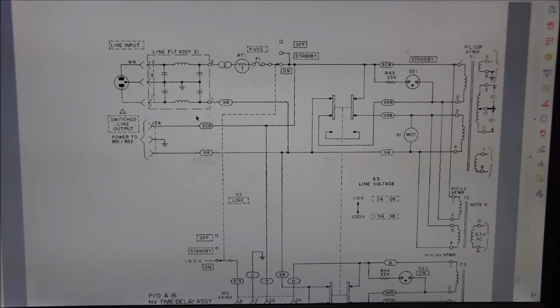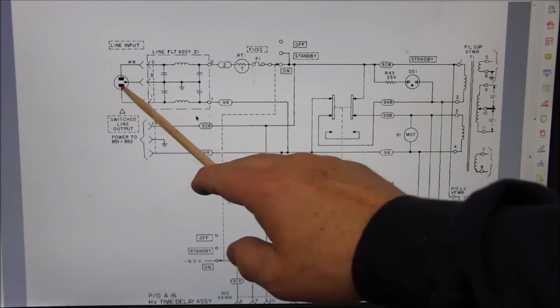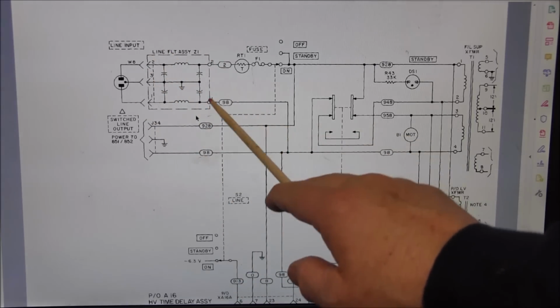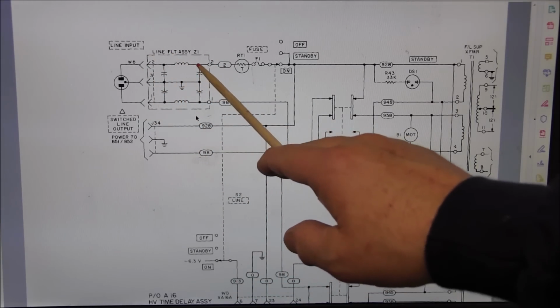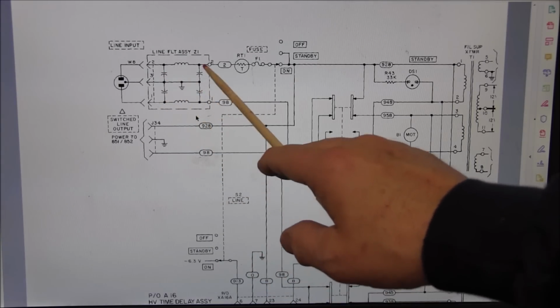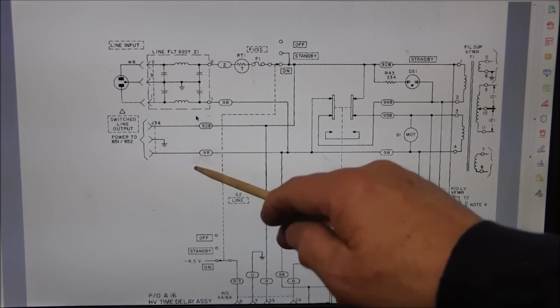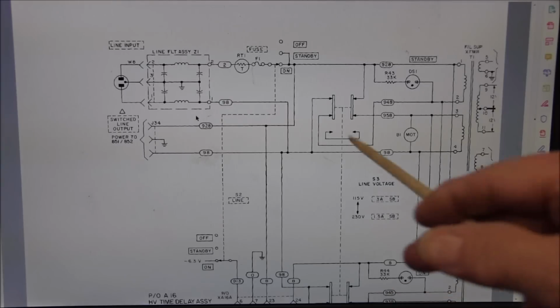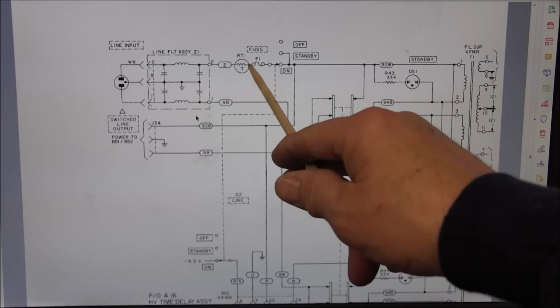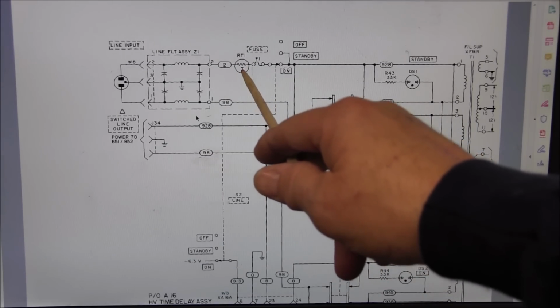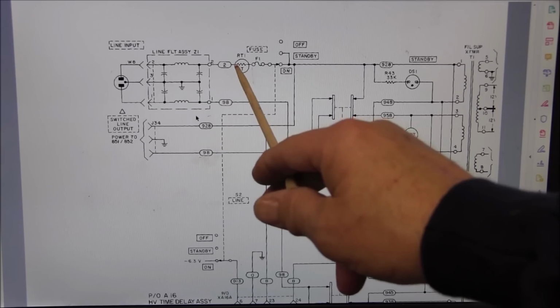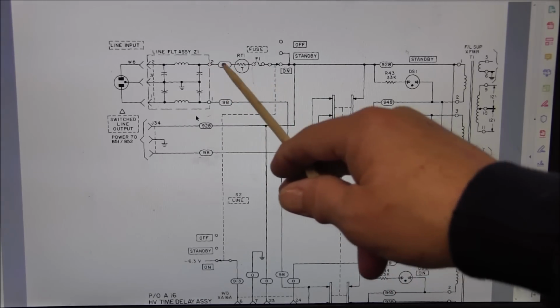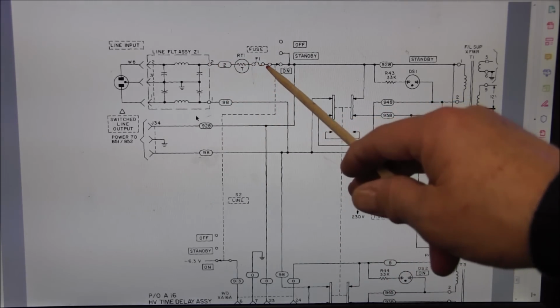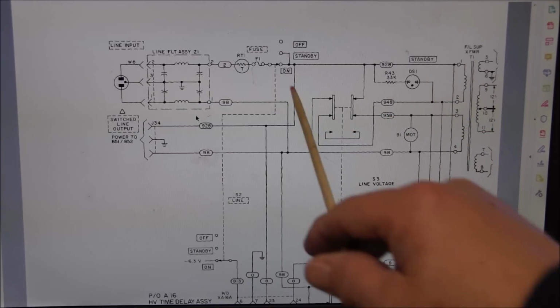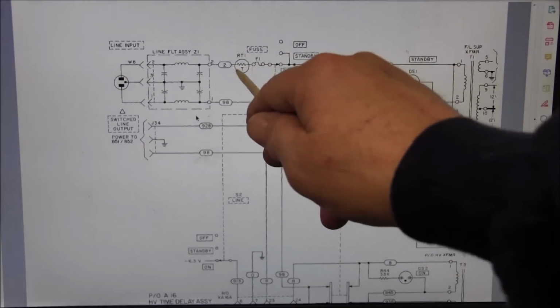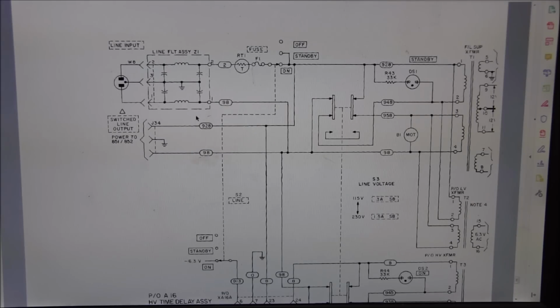We're looking here at the schematic and you can see the AC mains input, and this block is that line filter assembly, and inside of it are 4 capacitors, 2 coils. But more of a concern to me, not only are these capacitors, is this RT1, which is a type of thermistor, and they have been known to break down, and you can see it directly in the hot side path of the AC mains right just before the fuse. So that thing does concern me a bit.